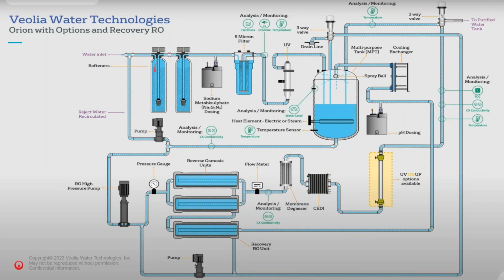We run it through twin softeners in series. We don't run them in parallel or in duplex because that has potential for some dead legs. So we run the water continuously through both of these units. The first unit sees 100% of the hardness, and the second unit picks up any slippage that may come through that first unit. So the second one regenerates every third regeneration of the first unit, as it sees less of a demand. And when this one is regenerating, we bypass round and the second softener takes the full load of the flow. So we don't interrupt any purified or cold WFI production into the tank.